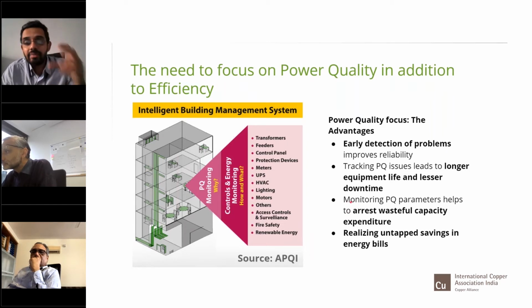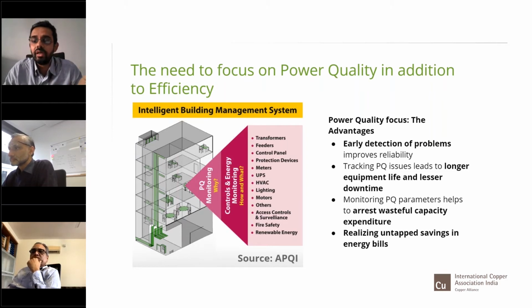Third, monitoring power quality parameters helps arrest wasteful capital expenditure. I've experienced this so often. I can give a live case I was just discussing prior to this webinar: a UPS not able to take a load more than 60 to 70% for certain air handling units. The facility owners or managers were contemplating just doubling the capacity of the UPS. But is that the right approach, or does it have to do with power quality that needs investigation to find the root cause? In the midst of live monitoring, we realized it had nothing to do with capacity — it was simply due to harmonics, and to how the UPS system had been designed. So arresting capital expenditure is important, and proactive power quality monitoring can help achieve that.